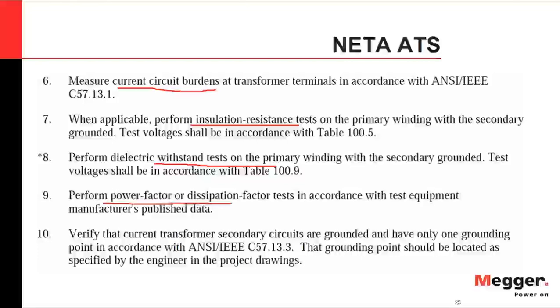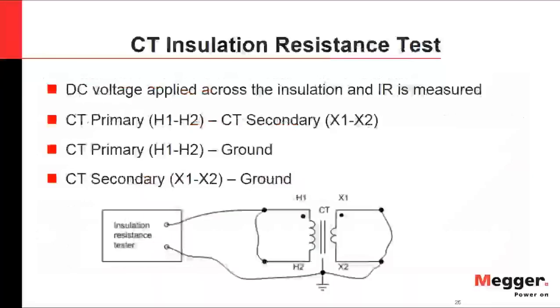For CT insulation resistance testing, it is typical practice to perform the test at voltages below 1000 volts. We create test electrodes by shorting terminals — in this case H1 to H2 — and the other electrode is typically X1, X2, and ground. Different parameters and configurations can be used. The goal is to confirm the current transformer can handle the voltage level at which it has been classified.